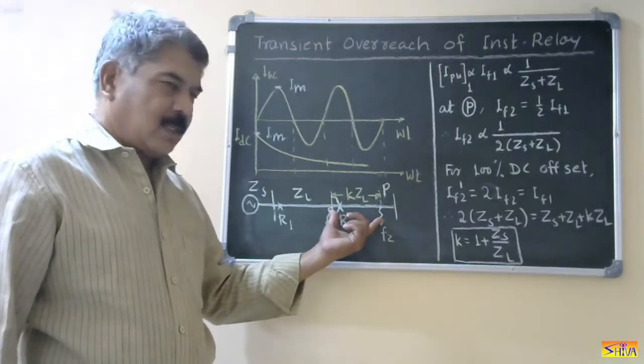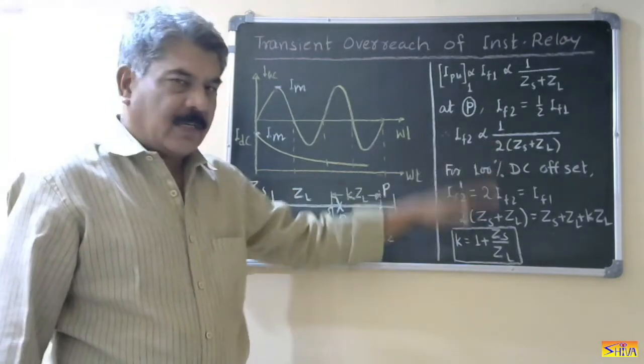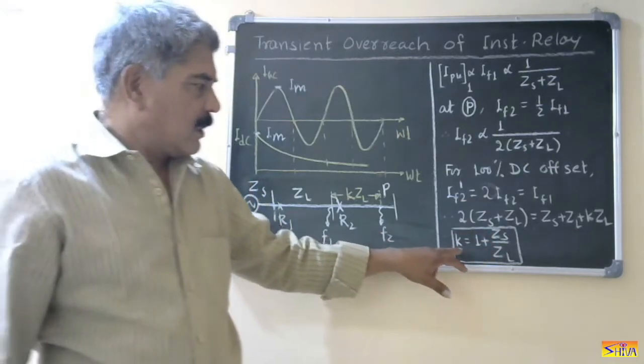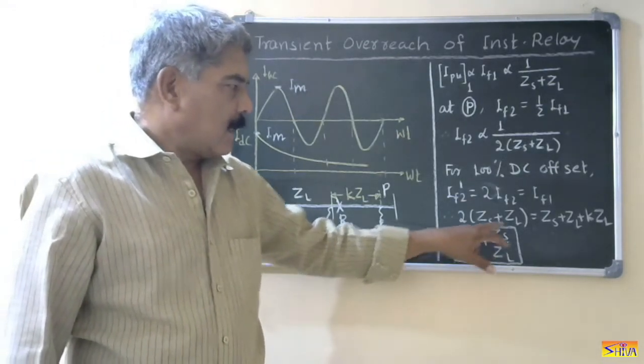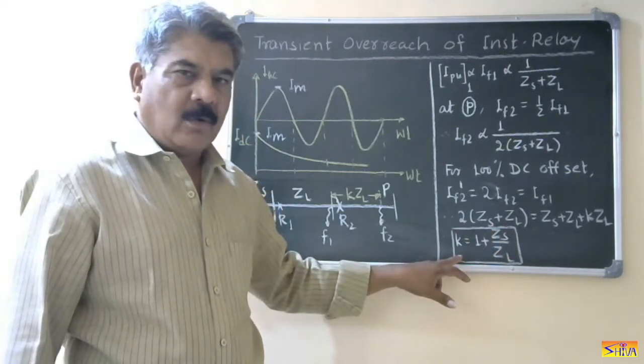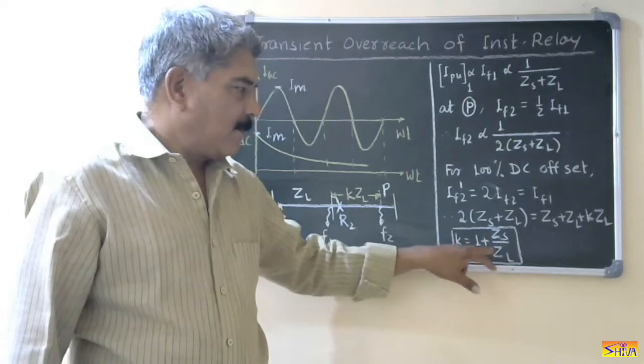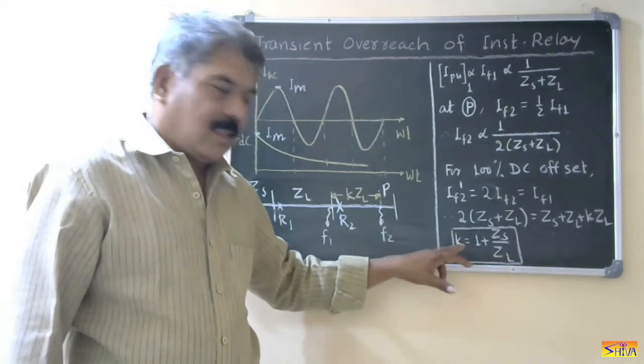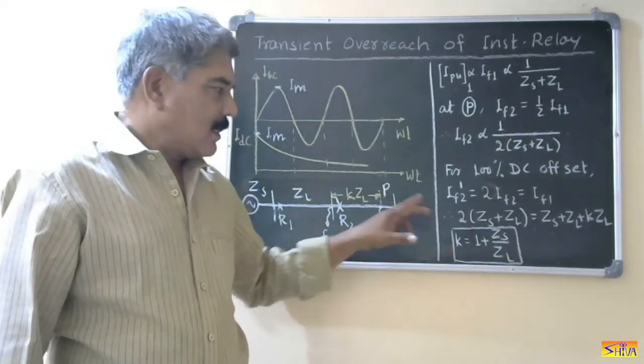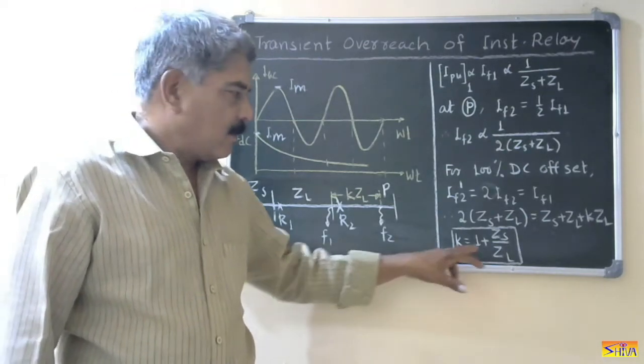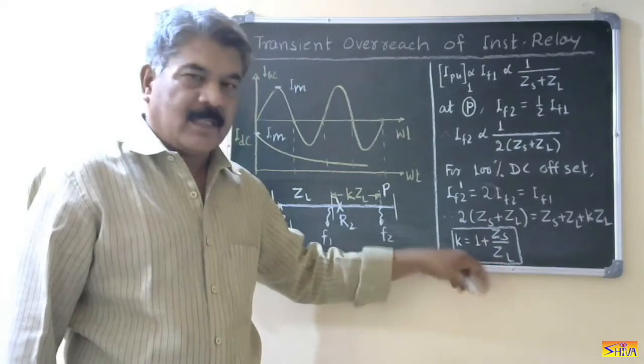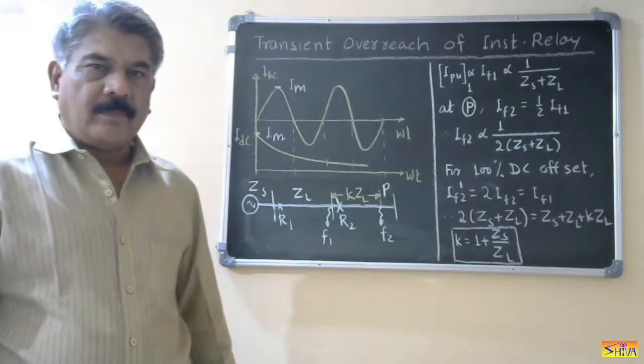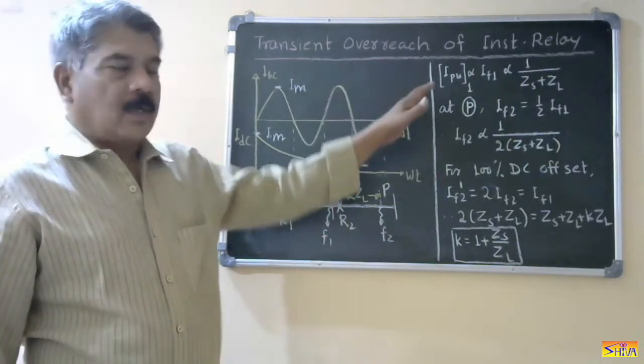In the worst condition the relay will reach up to this point. If the DC offset value is reducing, K is also reducing. From the equation K = 1 + ZS/ZL, larger the value of ZS, more will be the overreach. Therefore, instantaneous relay is not preferred when the ratio of source to line impedance is higher, because if it is higher, the overreach will be more. This concludes the discussion on transient overreach of the instantaneous relay.